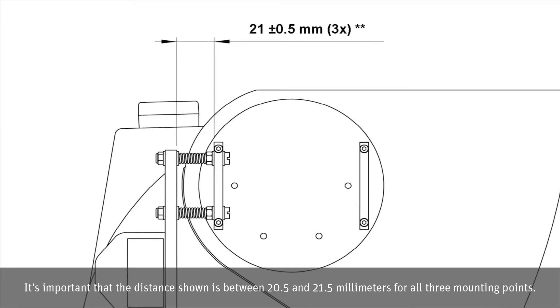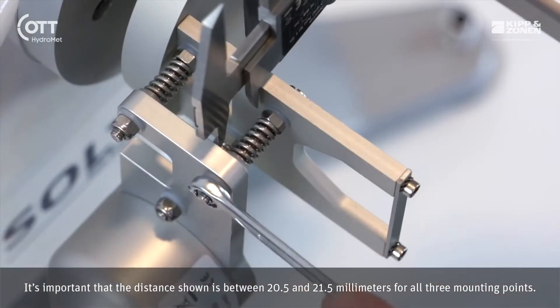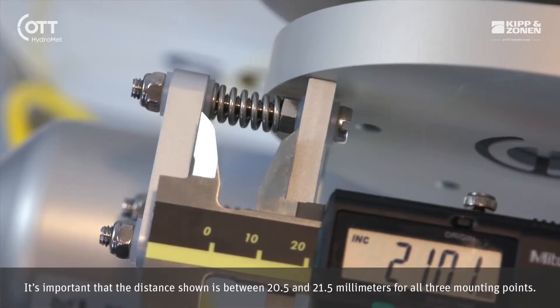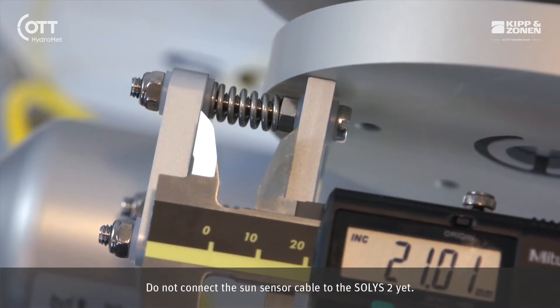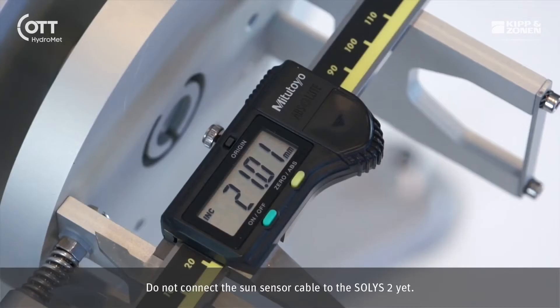It is important that the distance shown is between 20.5 and 21.5 millimeters for all three mounting points. Do not connect the Sun sensor cable to the SOLYS 2 yet.